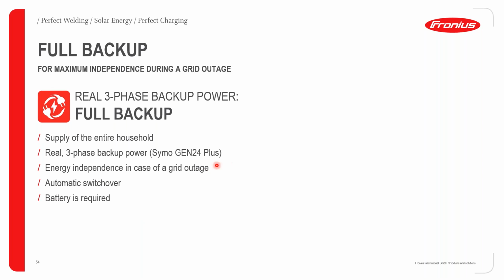What I should mention here as a quick fact, something that you need to bear in mind always, is that the Gen 24 Plus inverter is not a UPS kind of inverter whereby you have instantaneous transfer from grid failure to battery consumption, because it's a grid-tied inverter and must respect some grid codes for different countries. The Gen 24 inverter has a time lag of about 60 seconds between grid failure and when you are switched to power from the batteries. But on grid return, the connection back to the grid is seamless. That kind of measurement does not need to happen when you are connecting back to the grid after a grid failure.